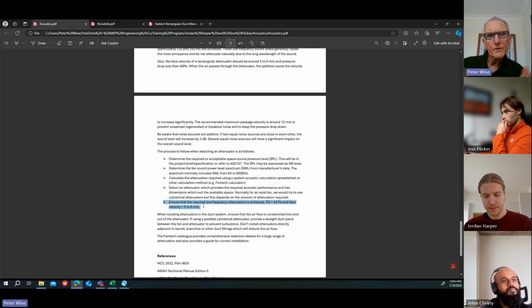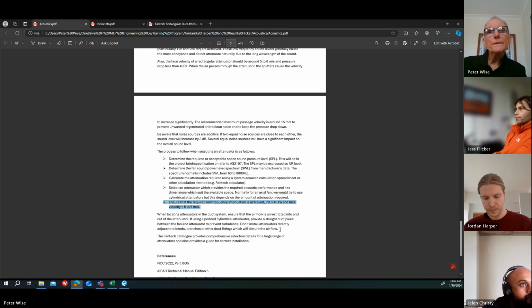If your duct velocity is 7 meters a second and you don't need a lot of attenuation, then that's probably going to be okay. But I just mentioned that as a bit of a guide to be aware of. In other words, don't have a duct that's running at 10 meters a second and then crashing into an attenuator and trying to squeeze the air through those narrow pathways to attenuate the sound, because it's not going to work very well. You'll end up creating a turbulence at the inlet and regenerating noise.